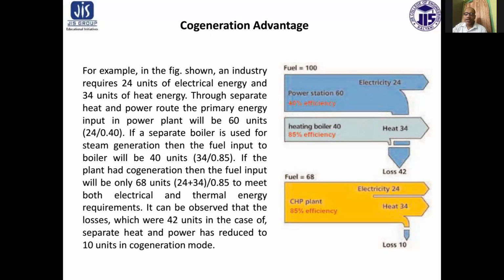Now, if the plant is cogenerating, then the fuel input will be only 68 units to meet both the electrical and thermal energy requirements, as in this case the efficiency of the cogeneration plant is taken as 85%. It can be observed that the losses, which were 42 units in total in the case of separate heat and power, have reduced to 10 units in cogeneration mode.